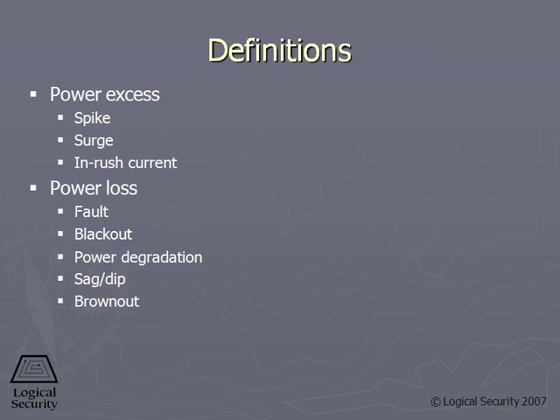Next, we'll look at the lower power situations. We have the power fault. Now, a power fault is generally where one of the three prongs of your AC system fails. So a power fault is where one of the three wires becomes disconnected. A blackout is where we have a complete power failure. This is no electricity whatsoever, no voltage whatsoever.